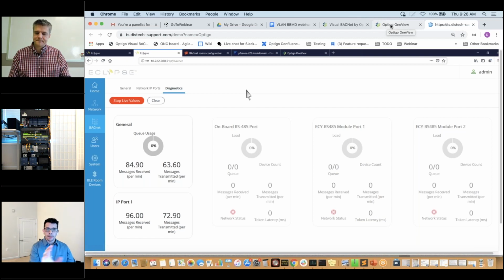Are you having a device go and read that point? Are you broadcasting that value out to the network because multiple controllers can use it? So it comes into how, first of all, are you consuming that data? Are you sending it, or is it being pulled? Is it a confirmed COV? So you have to look at how you're moving the data, and maybe how you set up your network helps you decide how to move that data.